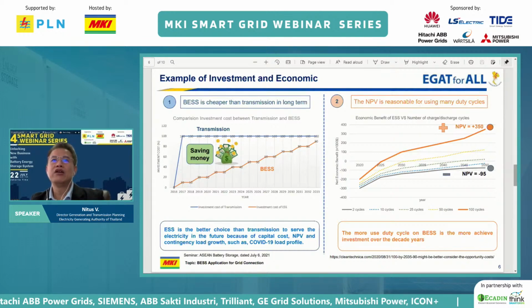On the other hand, using BESS can be planned in a short-term period, around 3 to 5 years, because the utility can adjust the sizing of BESS and the installation does not take a long time. In addition, in case the load profile does not grow as forecast, like in the COVID-19 situation, the utility does not need to purchase more battery to supply demand.